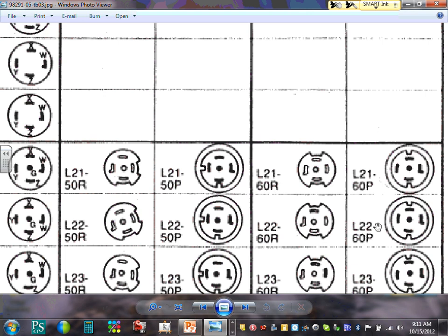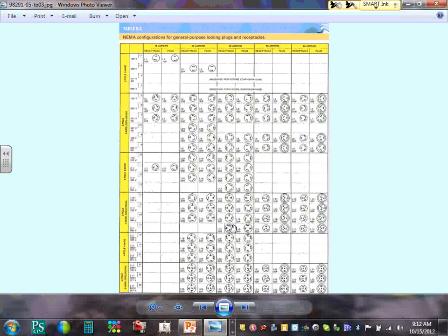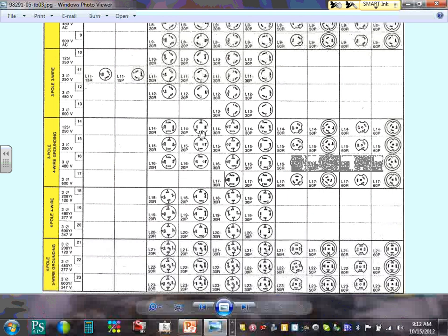These are locking type receptacles. 60 amp 480/277 is one example where you can use it for a portable generator all the time. As a matter of fact, we installed 200 amp. Hubbell makes bigger receptacles, 200 and 100 amp at 480/277. Okay, but specially designed. But that's the NEMA configuration. Any questions, guys? Any question about that? Does that make sense? Yes, no?